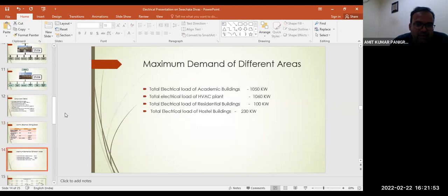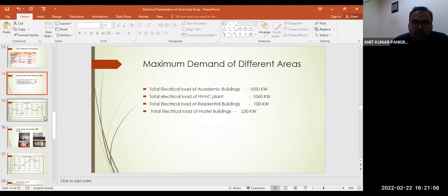So next, in the NISER campus, what are the different buildings and their maximum demand? If you take the total electrical load of the academic buildings, meaning physics, physical science, chemical science, library, mathematics, it is around 1050 kilowatt. The HVAC plant alone takes around 1060 kilowatt. All the residential buildings together are around 100 kilowatt, and in the summer season it goes up to 120, 130 kilowatt. And if you sum up the maximum demand of all the hostel buildings, it comes around 230 kilowatt.